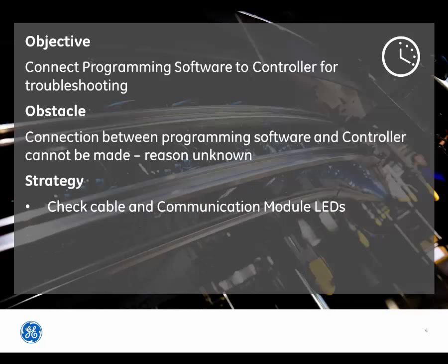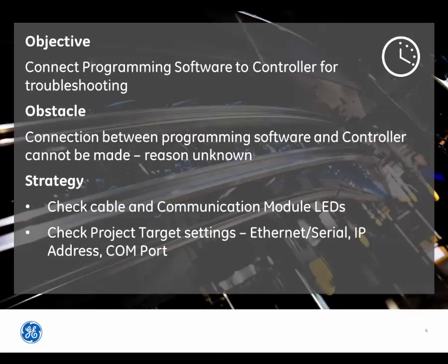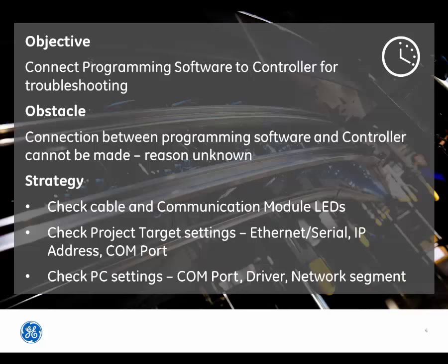The strategy to solve this issue is to: first, check the cable and communication module LEDs to see if communications is being attempted. Second, check the project target settings, such as the communications mode being Ethernet or serial, the IP address used by the controller, or the serial COM port being used to connect to the controller. Third, check the PC settings, such as the COM port, communications driver, or the PC's network segment.